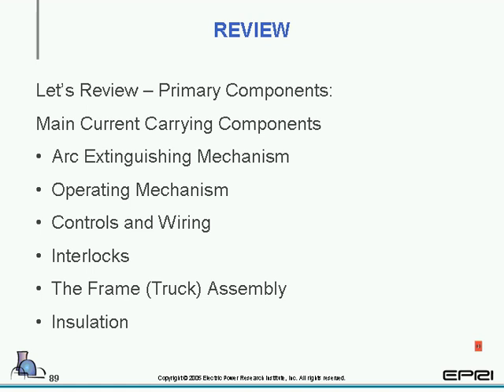Let's review. We have primary components: main current carrying components, arc extinguishing mechanism, operating mechanism, control wires, interlocks, frame, truck assemblies, and insulators. And Gene, if you would leave it on this slide. Again, this is something else you may be seeing later on, possibly in a quiz or something. So again, primary components of the circuit breaker include main current carrying components, the arc extinguishing mechanism, operating mechanism, control wiring, the interlocks, the frame, truck assembly, and the insulation.